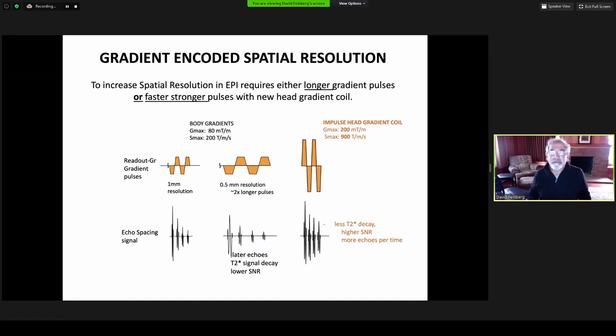This leads us to why we want a stronger, higher, powerful gradient system. The net gradient area can be doubled using taller pulses instead of longer pulses. Therefore, there's less T2-star decay, higher signal-to-noise in all the signals, and more echoes per unit time.